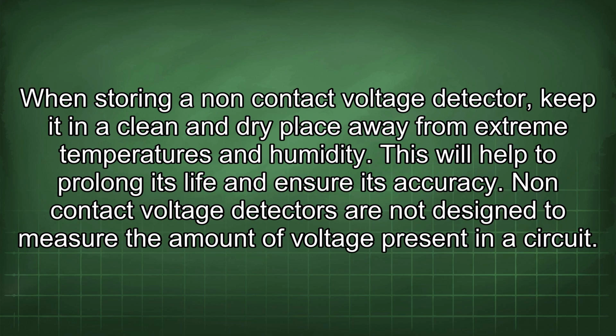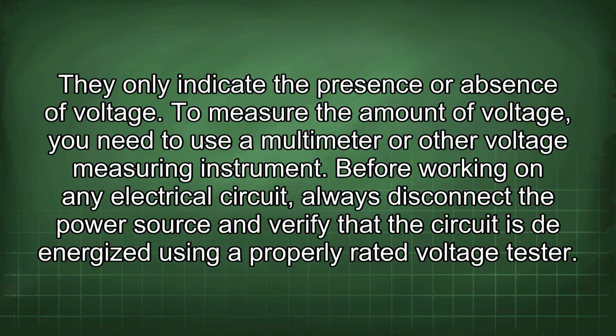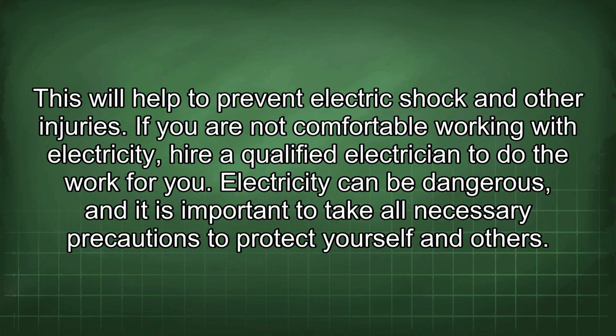Non-contact voltage detectors are not designed to measure the amount of voltage present in a circuit. They only indicate the presence or absence of voltage. To measure the amount of voltage, you need to use a multimeter or other voltage measuring instrument. Before working on any electrical circuit, always disconnect the power source and verify that the circuit is de-energized using a properly rated voltage tester. This will help to prevent electric shock and other injuries.